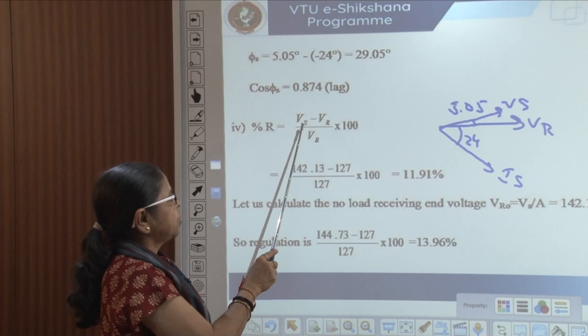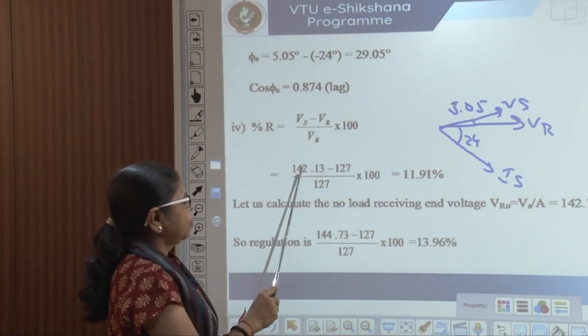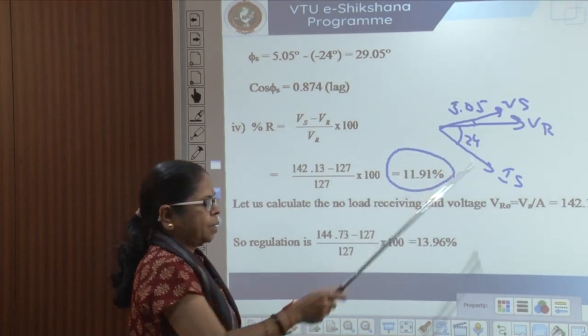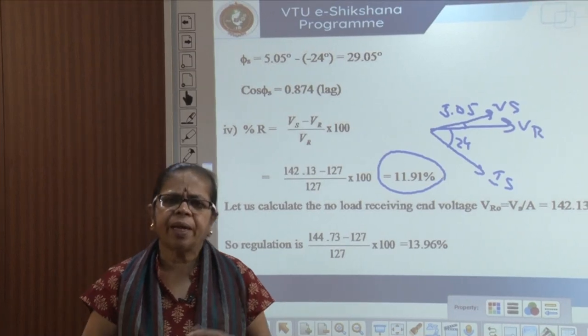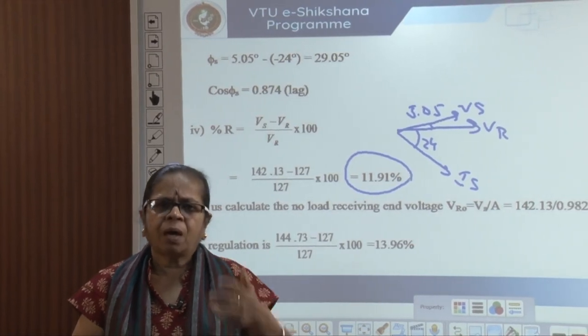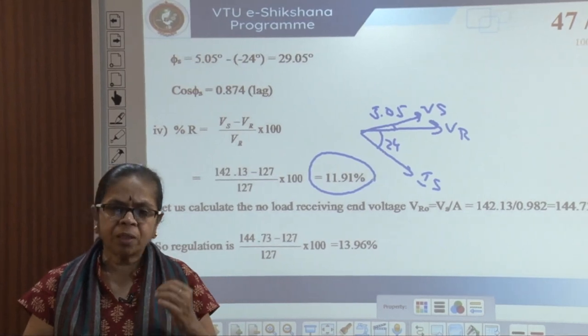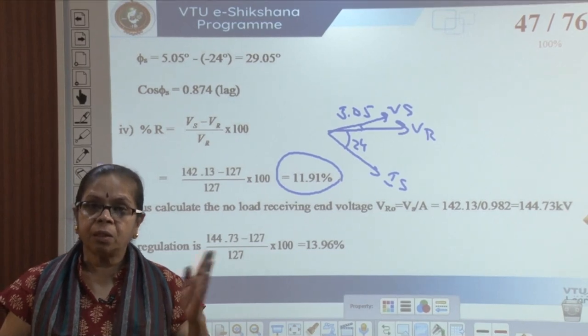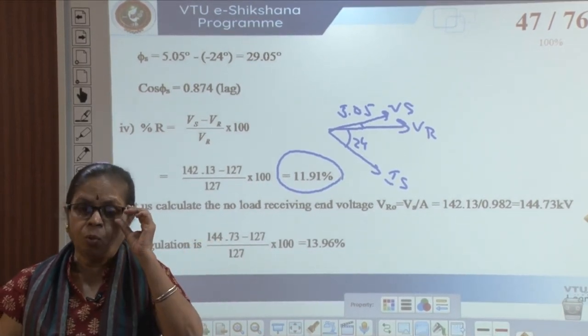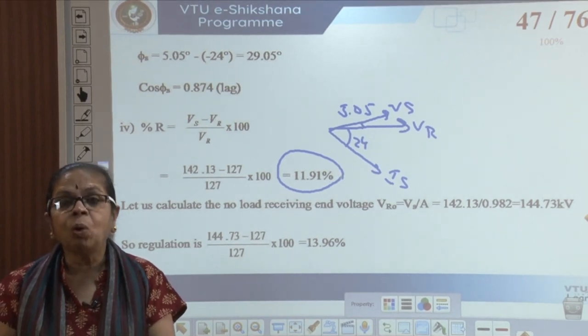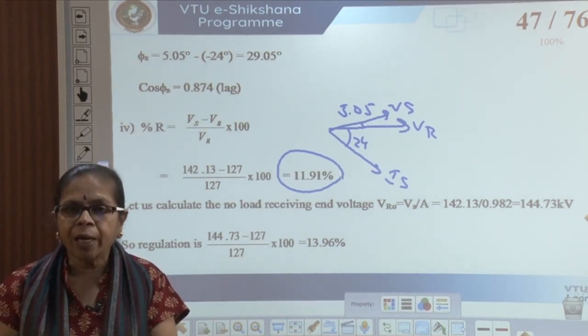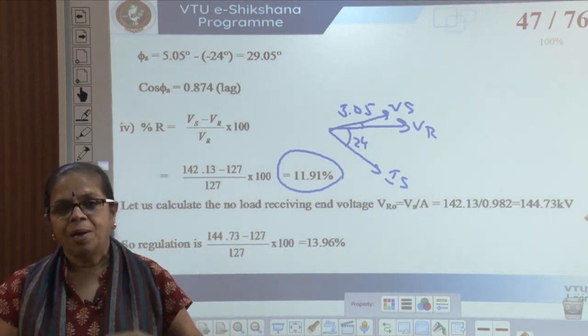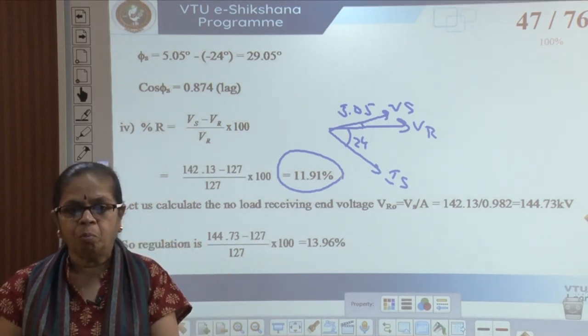Percentage regulation is (Vs − Vr)/Vr, giving 11.91%. Can you see that the regulation is higher? Higher regulation means it is bad, because it means there is a lot of difference between the sending end and receiving end voltages — so regulation is poor. A higher value of regulation implies poor regulation. This is because of the longer line — as the line length increases, the drop is more.